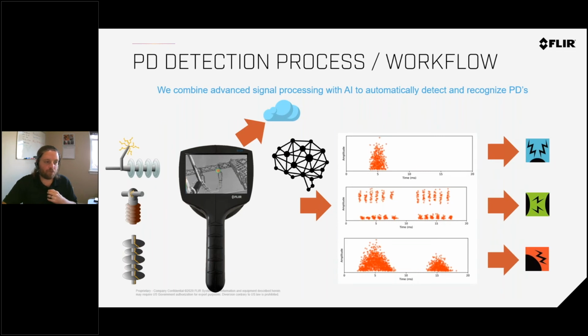You can have one of three different things: discharge in the air, discharge between two components that are close to each other, maybe bouncing off one another, and the most dangerous one, discharge internally. You have different icons so you know what you're looking at, because there's going to be a certain amount of discharge that's just normal and not harmful. But once we put this into the AI for analysis, we'll know whether it's harmful or needs to be addressed.